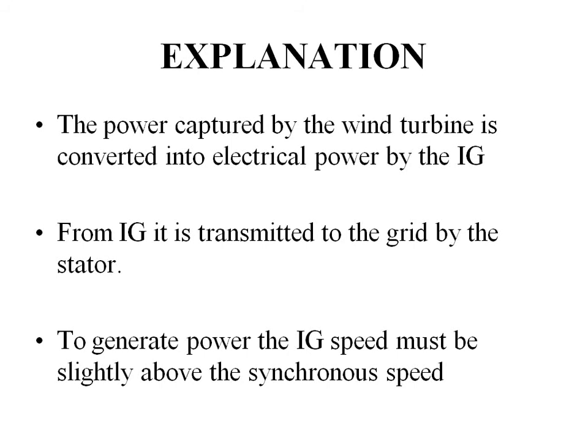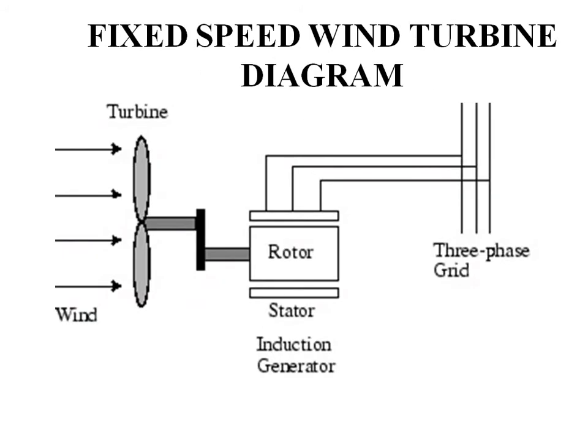The power which is taken by the turbine is converted to the electric power by using the induction generator. The induction generator will supply energy to the grid. The power generated by the induction generators to be fed to the grid makes it necessary that the induction generator machine operates above synchronous speed. Otherwise, instead of supplying power, it may absorb power from the grid. That is called motoring mode.